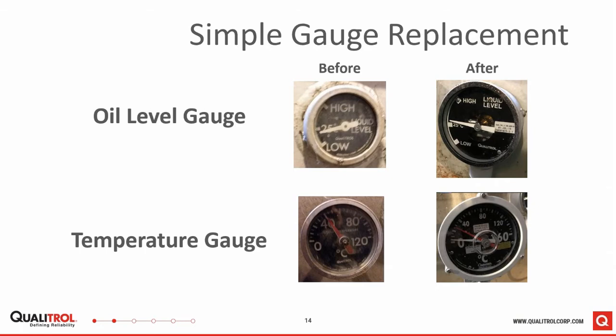output. For temperature gauges, again, those are typically installed in wells. So again, when you remove a temperature gauge, no oil comes out of the transformer, and so you don't need to lower the oil level. You simply remove the gauge out of the well, you install a new direct mount gauge into the well, and the new gauge has an analog output so that we can see the temperature remotely for the temperature gauges on the switching compartment and the main tank. You can go to the next slide, please.